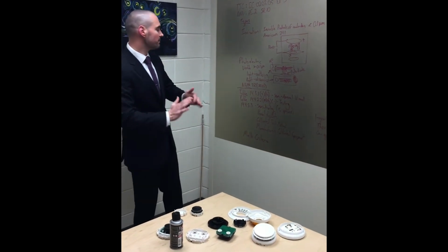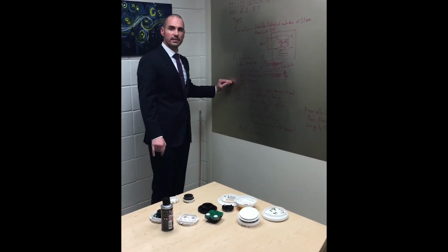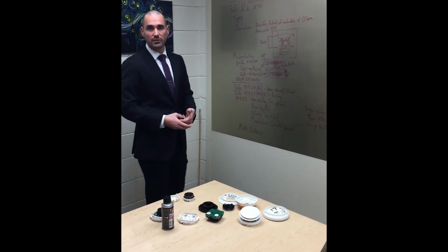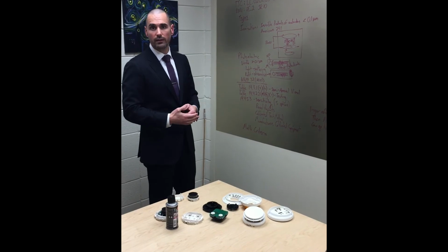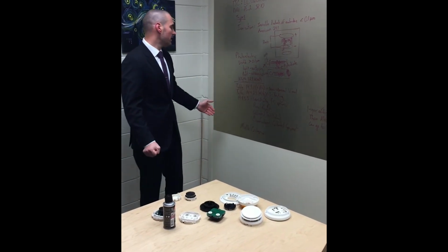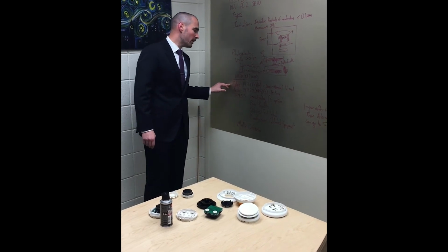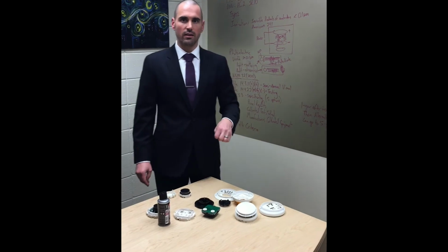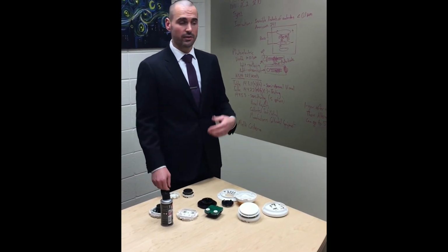So for our testing, NFPA 72 2010, as always, we're using the 2010 edition because CMS has adopted the 2012 version of Life Safety Code, which references the 2010. Table 14.3.1(9)(h) requires that smoke detectors have a semi-annual visual inspection.